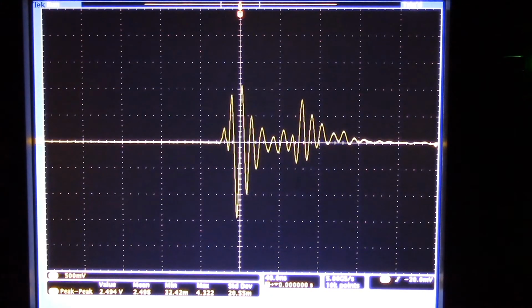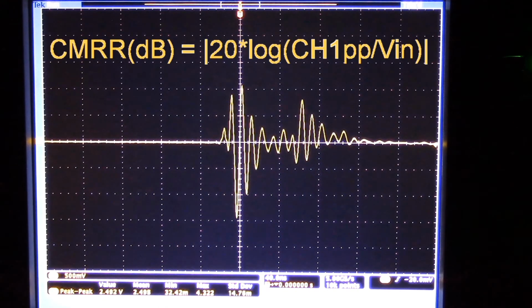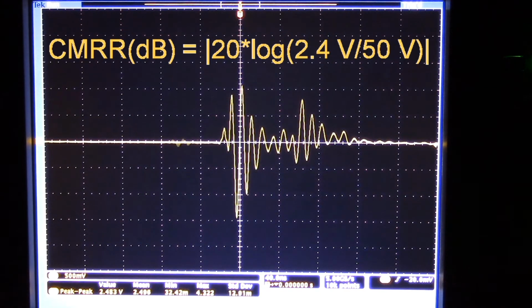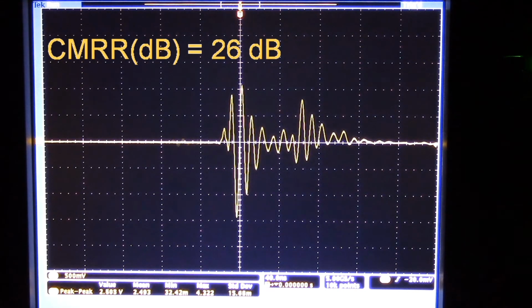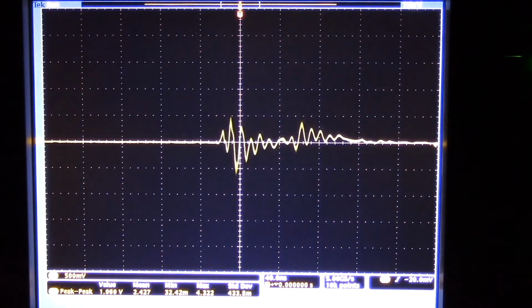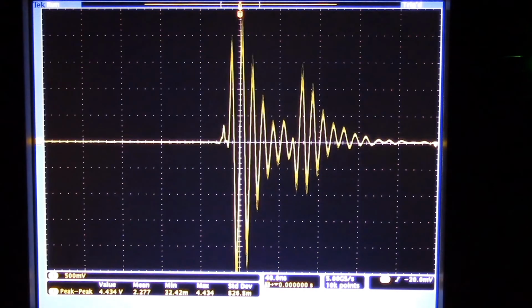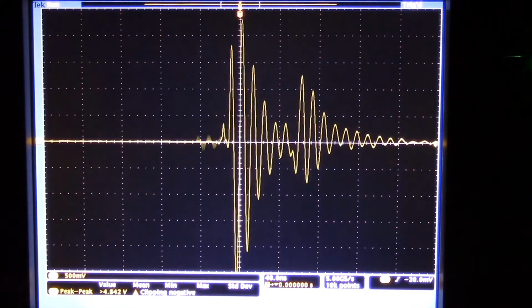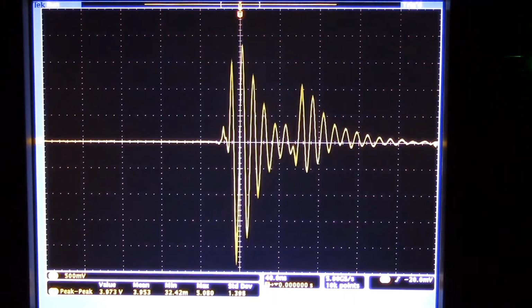Ideally what we would see is a zero signal, a flat line. What we're measuring on the scope right now is 2.4 volts peak to peak. Now looking at our common mode rejection ratio calculation, this gives us a common mode rejection of approximately 2.4 divided by 50, take the log, multiplied by 20. So right now what we're seeing is a common mode rejection ratio of about 26 dB. That's worse than 20 to 1. And you can see as we move the cables around that the signal changes significantly. So depending on exactly where the probe is positioned and the lead dress, the signal can change from less than 2 volts to almost 4 volts, over 4 volts.